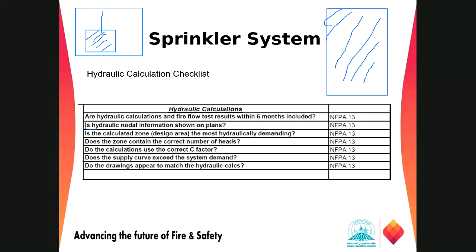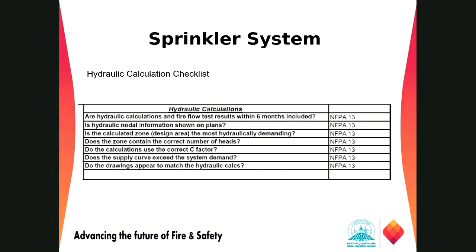That's it. Like this is our sprinkler system, right? This is our, suppose, T arrangement. This is sprinkler 1, this is second, and this is third and fourth. So they will start noding from this one all the way to the riser, right? So no need to give the noding of the non-hydraulically demanding area. If this is our demanding area, we need noding for this area only.